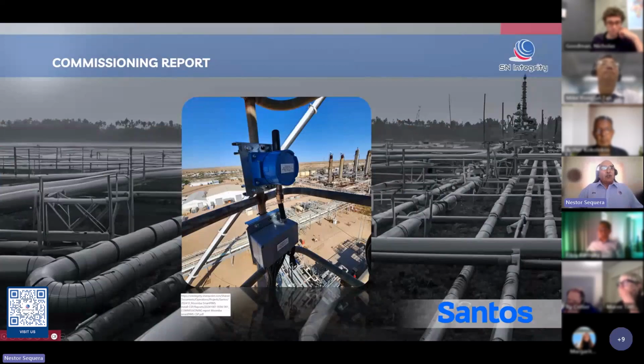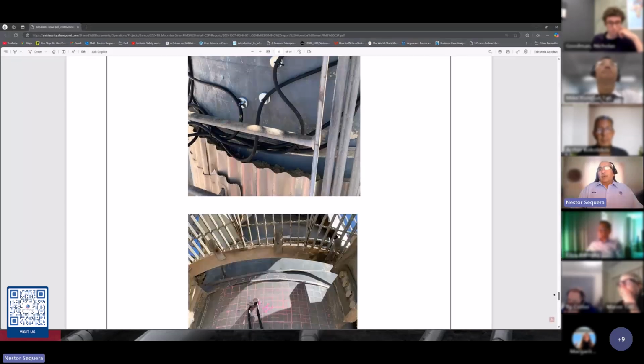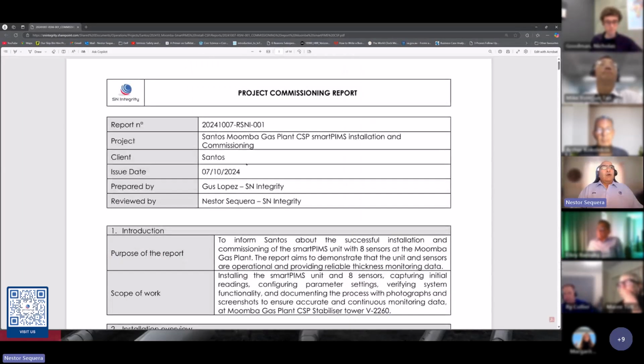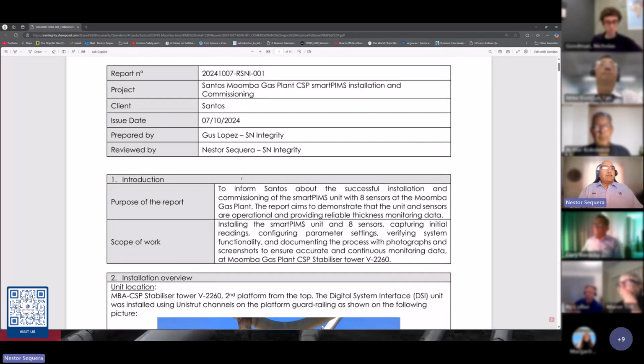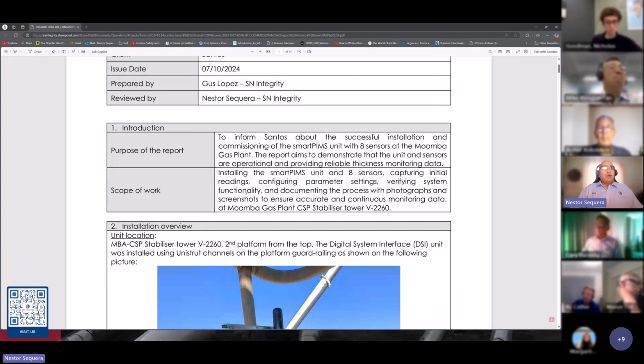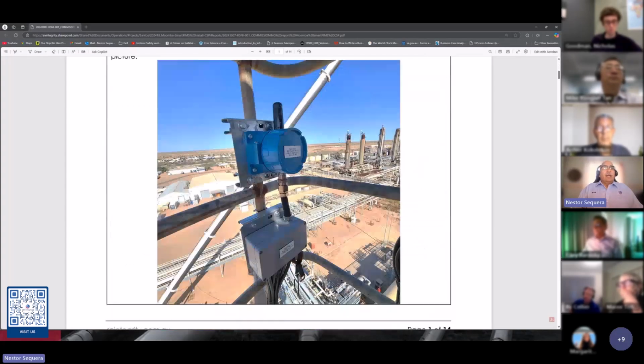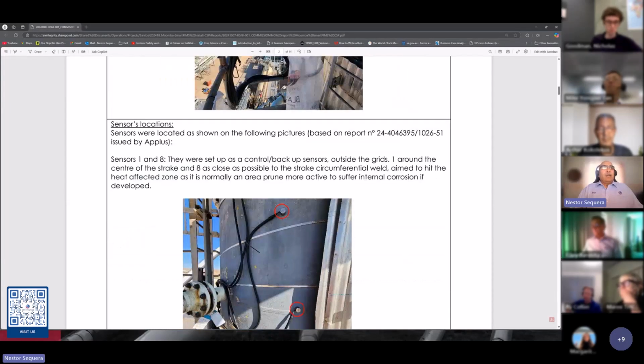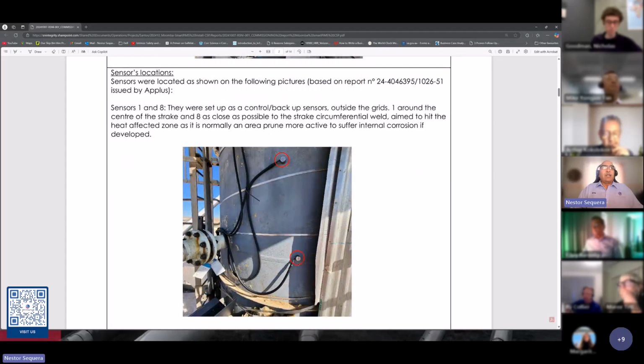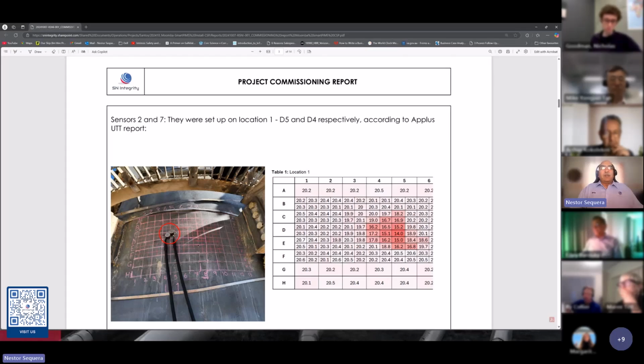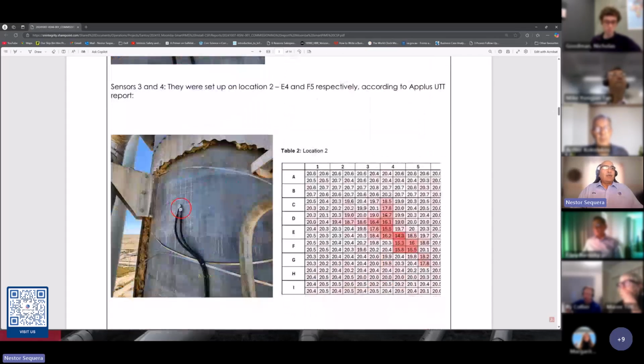After we finish the job, we present the customer with a full commissioning report where all the job that we did gets documented for future traceability. So we inform the purpose of the report, the scope of work that was undertaken, how the unit was installed into the handrail and security bolting on position, and the cable running, where each sensor was installed. For instance, 1 and 8 are the controlling sensors, so they were put onto the nominal wall thickness location, where the others were put on based on the map that we were provided, where we are targeting the lower points on the map that the customer provided us with. All of that was documented for future reference, so they know where we are following things in the tower.